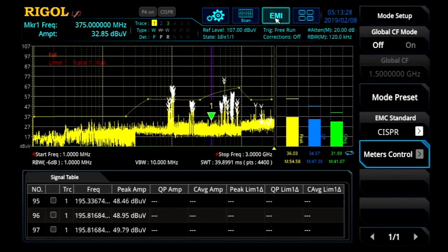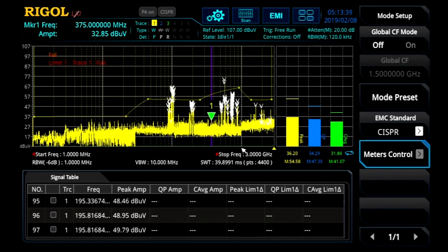Let's take a quick look around and familiarize ourselves with some of the capabilities and terminology we use in the EMI measurement application. Once we're in EMI, we see this scan region here. This is configured as a log scan, scanning from left to right by frequency for our EMI test.